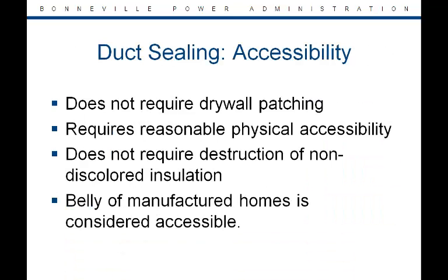The PTCS specification says that all accessible ducts shall be sealed. A location is considered accessible if it does not require drywall patching, is within reasonable physical reach, and does not require destruction of non-discolored insulation. Ducts do not have to be brought inside of the conditioned space. The belly of manufactured homes is considered accessible.